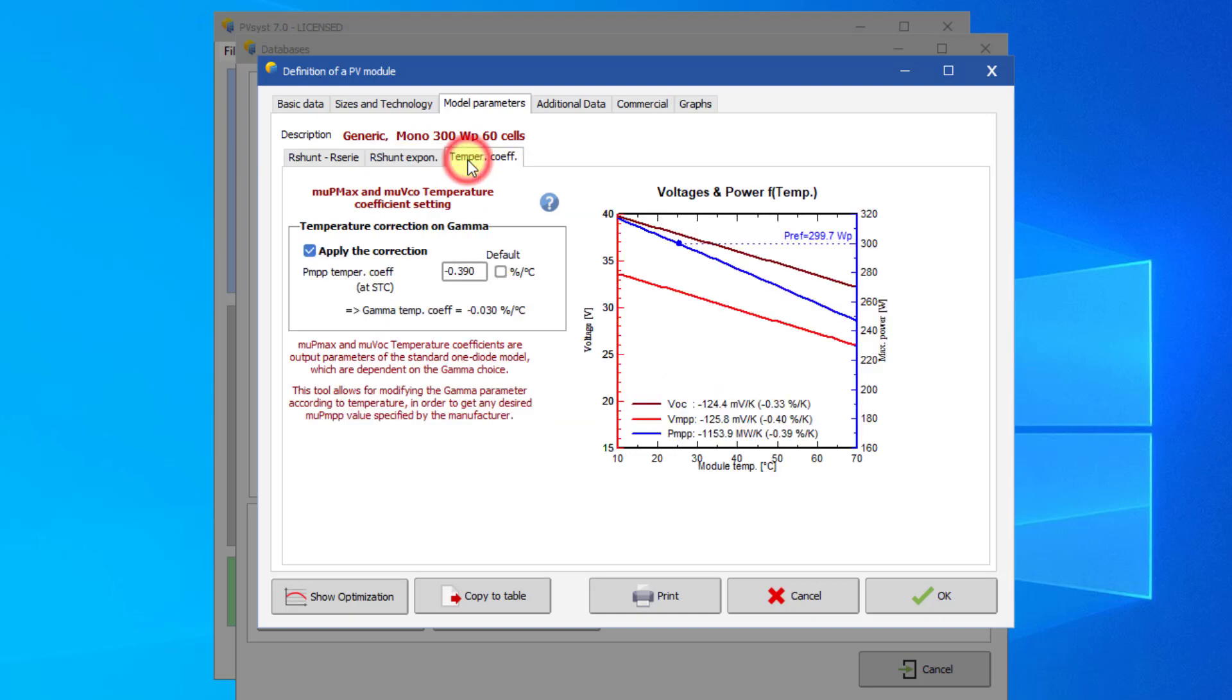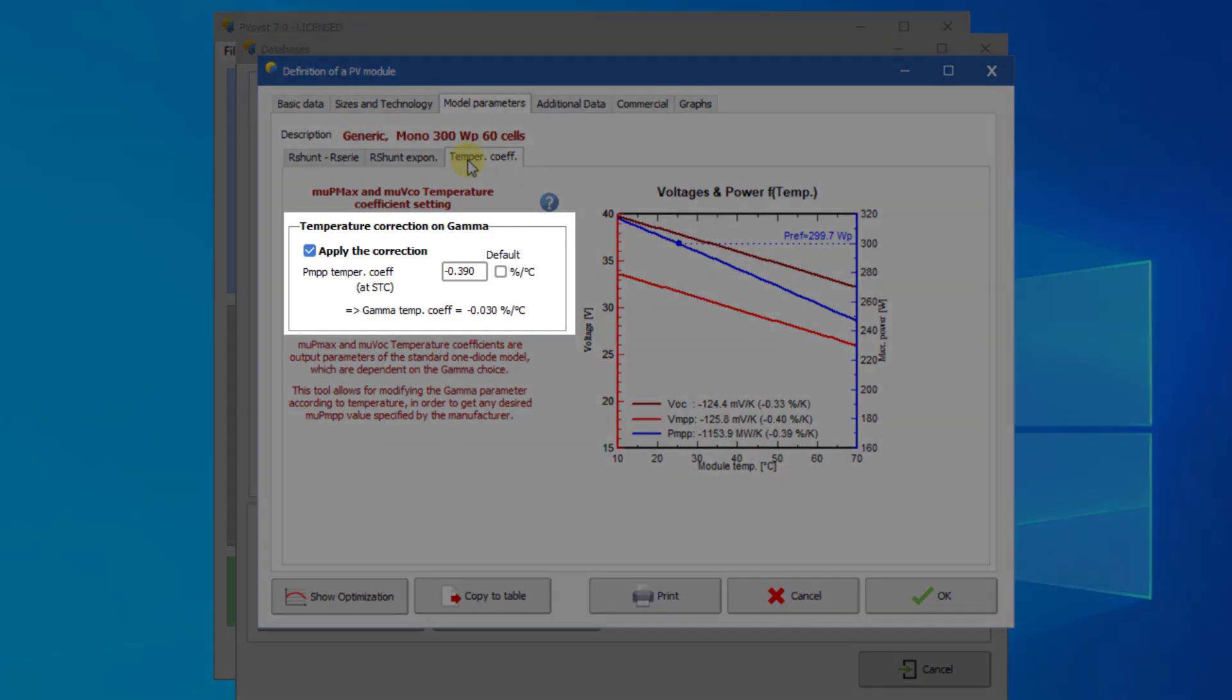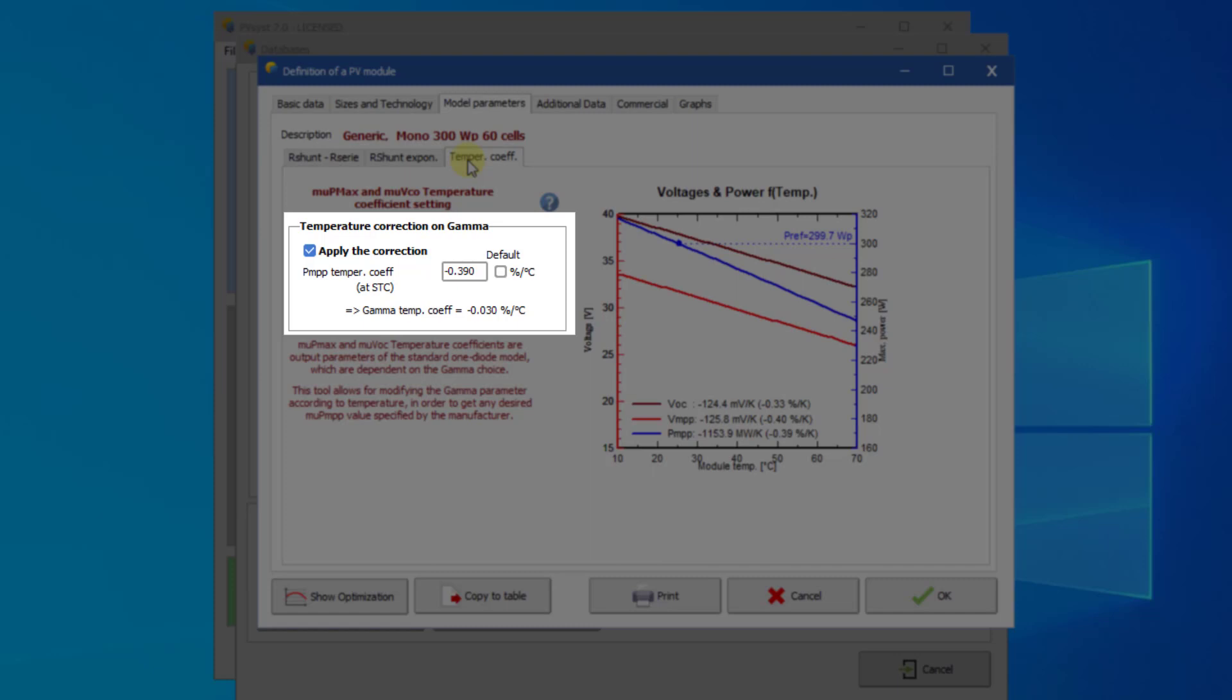The temperature coefficient page describes the temperature dependence of the maximum power point. Here, you should enter the PMPP temperature coefficient as given in the datasheet, where it is usually called gamma. This is a fundamental parameter for the simulation. PVSYST slightly modifies the standard one diode model to ensure that this value is exactly matched.